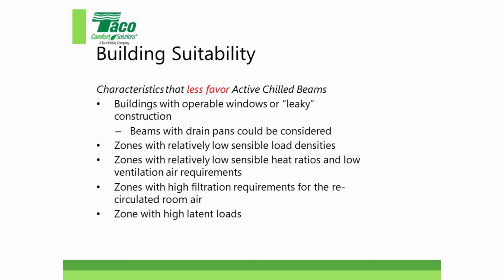So if there are high infiltrations or a high latent load in a building or zones, you don't want to use this as well. The same goes for leaky windows. I've worked on some projects with engineers that we work with, our reps, where they were going to put in chill beams and have operable windows. There are ways to shut the system down, but that adds complexity. I tell people, I used to be an engineer for a consulting firm. I like to keep things simple, and if you add complexity to a system, you could be asking for trouble, right? Yes, you can open a window and boom, it's going to shut the system down, but that's just adding complexity. People can tell you that you can do it, and yes, you can, but it's a personal choice. I probably wouldn't recommend doing something like that.